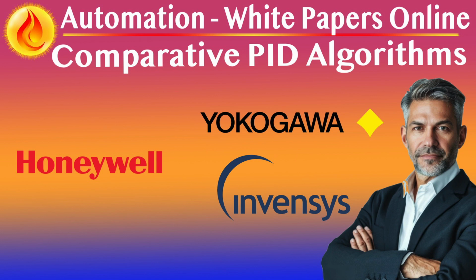Integral action, offset elimination with nuanced effects. Integral, or reset, action removes steady-state error but behaves similarly across algorithm types once tuning units are aligned. However, differences emerge in anti-reset windup handling, how controllers behave when output limits are reached. Although often subtle, these differences impact performance in systems with saturation-prone valves or long dead times.